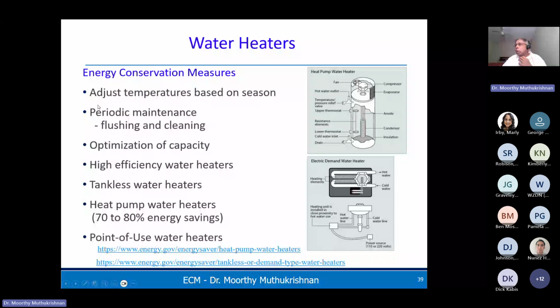Optimization of capacities matters too. You don't need a big water heater for a small room or building, so try to optimize it to save energy. There are also high efficiency water heaters available now, including heat pump water heaters, which save about 70 to 80% of energy. We can also use point of use water heaters, installed under the sink instead of a centralized one, avoiding the need to carry hot water all the way from the heater to the sinks or showers.